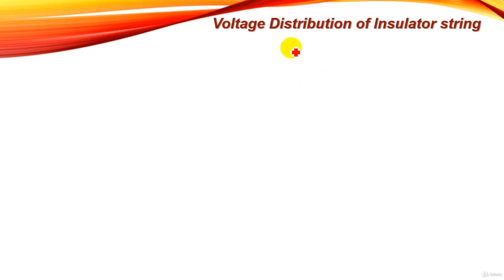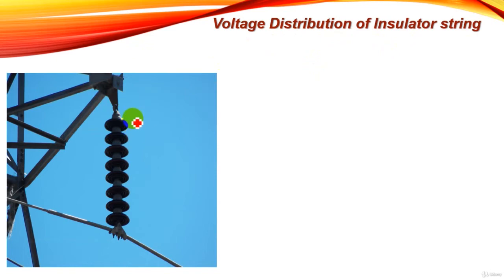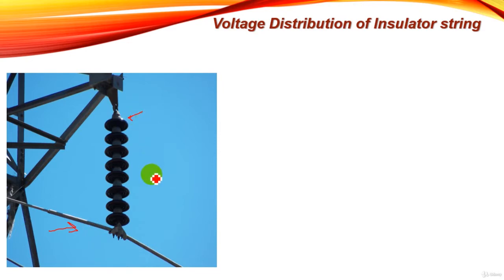In this tutorial we will understand how to determine the voltage distribution of an insulator string. Here we have an insulator string consisting of 8 units, which holds and carries the high voltage conductor. For example, if the high voltage conductor holds a voltage of 66 kilovolts, the whole insulator string should hold that same voltage. We want to know what voltage each unit of the insulator string holds.